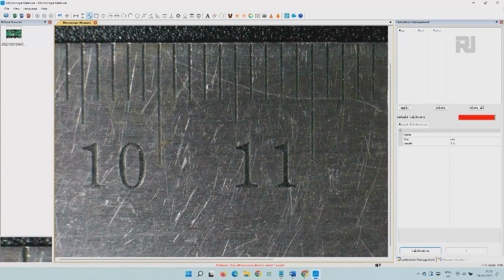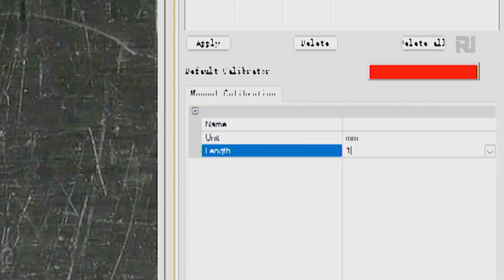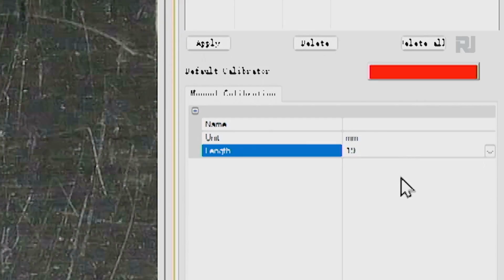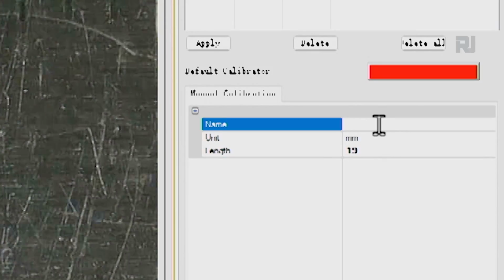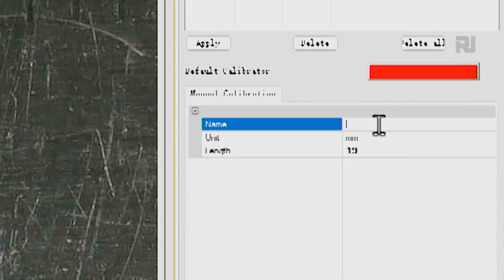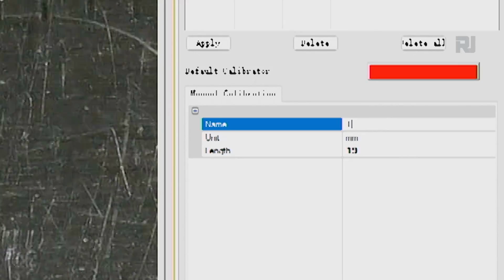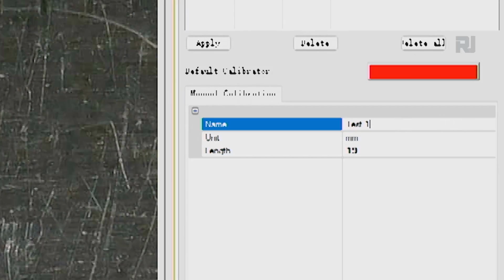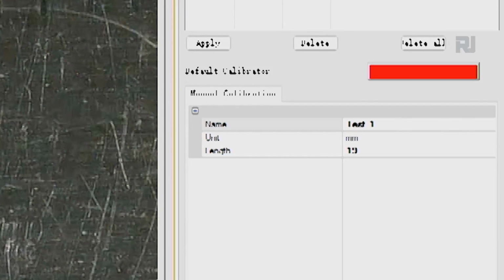Let me put it here at the middle, and up to here it's 5, up to here is 15, 16, 17, 18, 19. Let's put it here and click. As you can see, it shows 185. That's incorrect. Enter 19 here. We can name it, for example, test 1, and then calibrate, finish. So now calibration is done. Now it shows 19 millimeter.